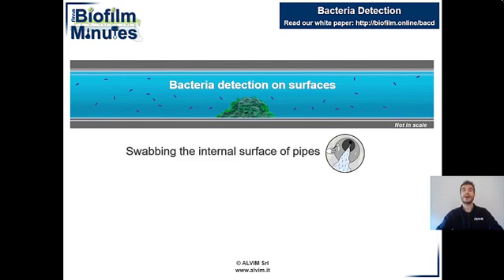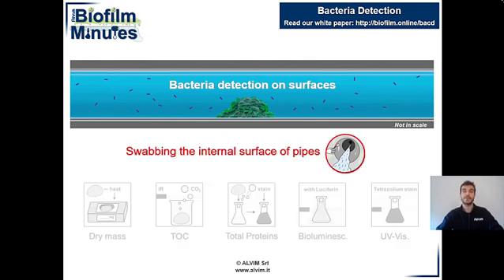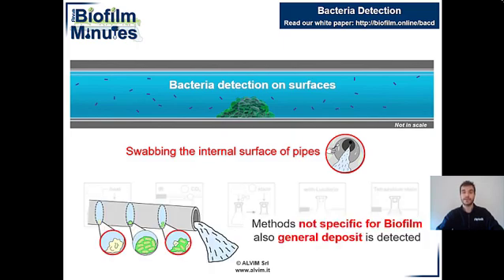Biofilm detection techniques generally require to access the line and swab the internal surface of pipes to collect a sample of biofilm. This sample can be subject to indirect methods of analysis, meaning that a correlation of biofilm presence with, for example, dry mass, total organic carbon, total proteins, and others is made. Of course, it is not comfortable to directly access the line to be informed about biofilm presence. In any case, indirect methods can detect biofilm as well as many other kinds of deposits and thus cannot furnish a representative indication.